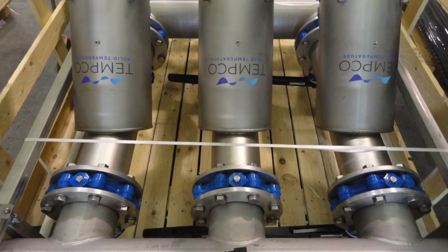When dealing with fluids containing suspended solids, we can implement different strategies to avoid contamination. One of the key aspects is filtration. Filters act as a bottleneck in heat exchange by reducing the flow rate of water, leading to pressure losses that require higher pumping pressure. However, they play a vital role in protecting us from contamination, making it crucial to have them in place for ensuring water safety and quality.